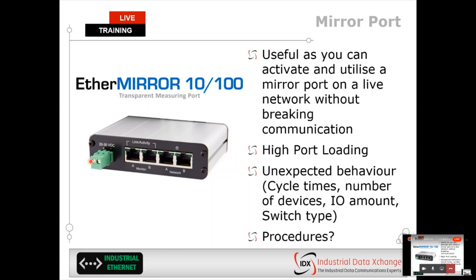Any time I need to tap into that network to do diagnostics without stopping the controller, without stopping the connection, I can simply plug my diagnostic tool directly into my monitor ports, do my diagnostic analysis, unplug, and the network is unaffected. Very useful for networks where you cannot stop the network whatsoever.